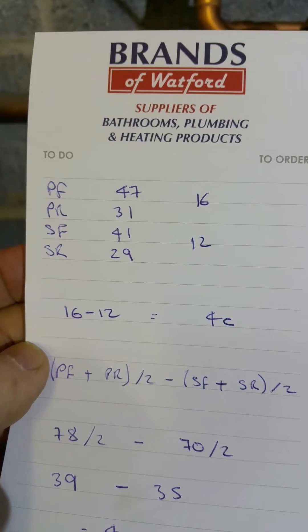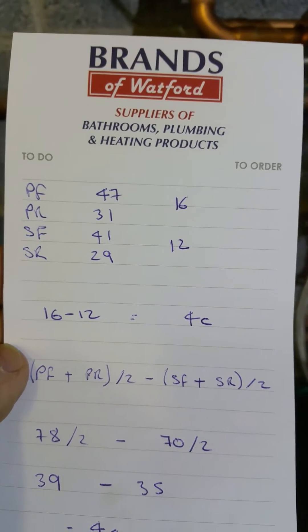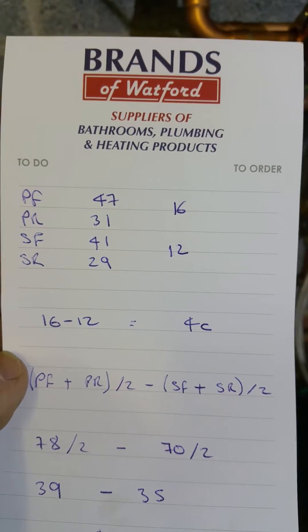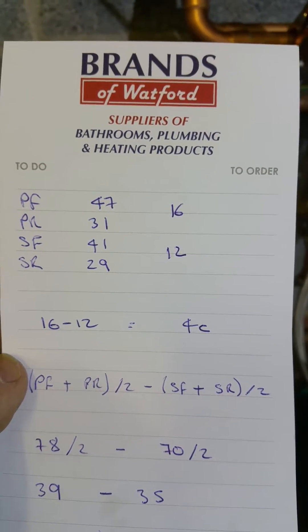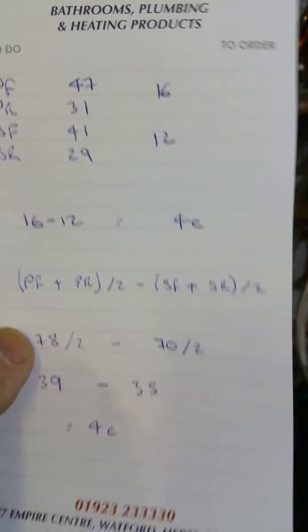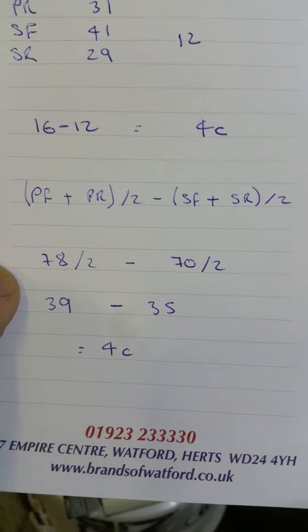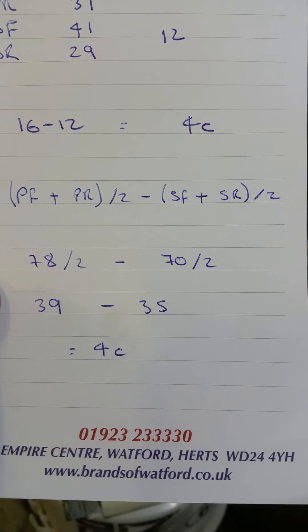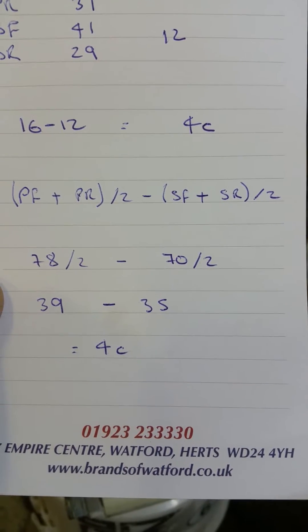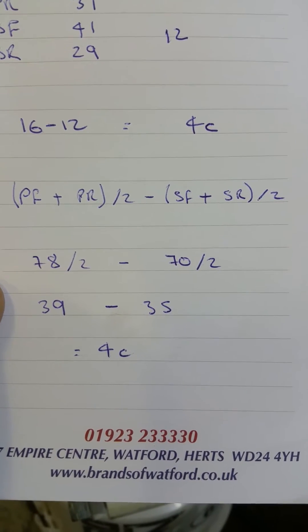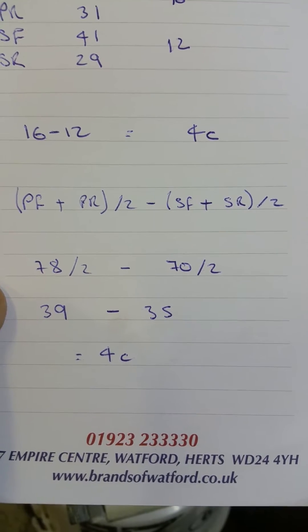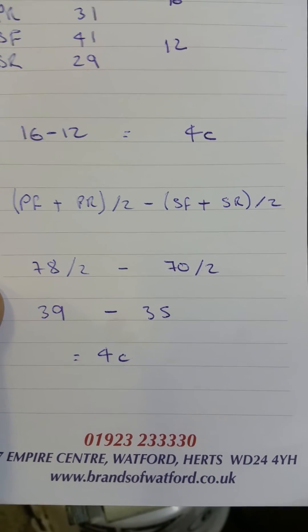I tried a calculation — I haven't studied this further — but 16 minus 12, which is the difference between the delta Ts, came up with a difference of 4 degrees centigrade. I wasn't sure if it's the same principle as the actual formula from the book, which is: primary flow plus primary return divided by 2, minus secondary flow plus secondary return divided by 2.